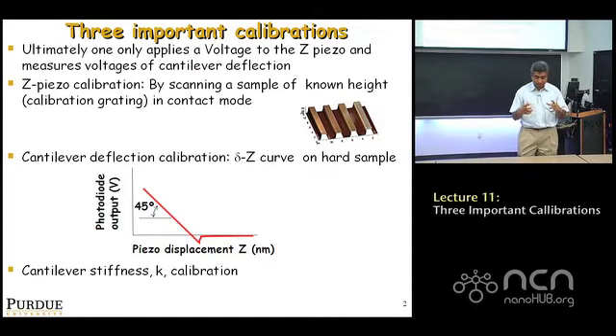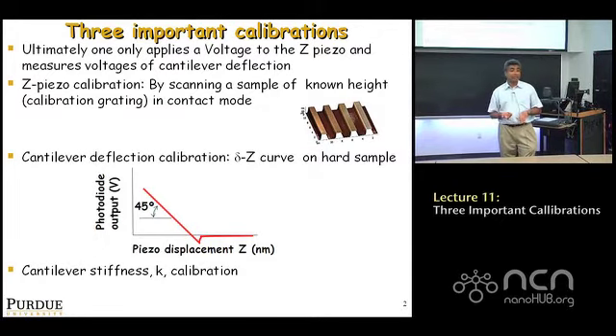Now, you have to keep in mind that in an AFM, when you move the cantilever close to the sample, you're applying a voltage to a piezo actuator, right? But how do you know how much the piezo actuator moved? So, in the previous examples in the last class, we talked about F versus Z. Z was somehow magically always in nanometers. Well, how do you know that? How do you know how many nanometers it actually moved forward by? This is an important question.